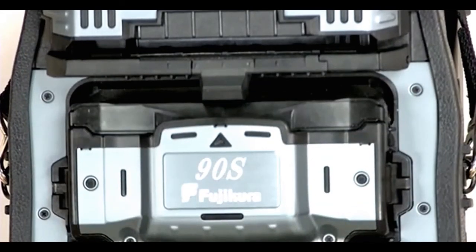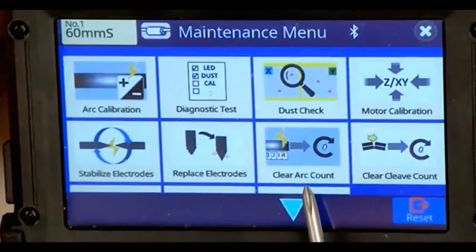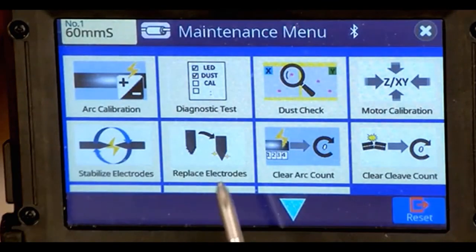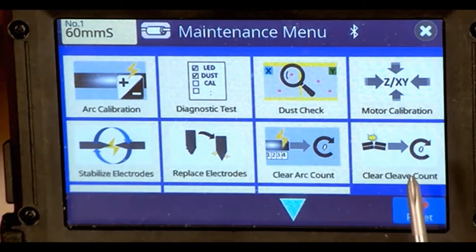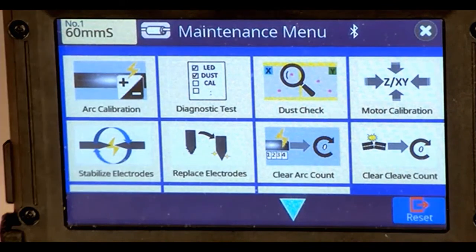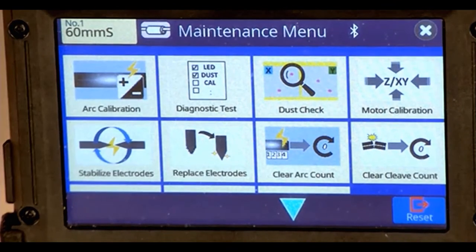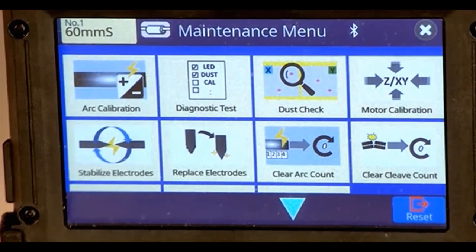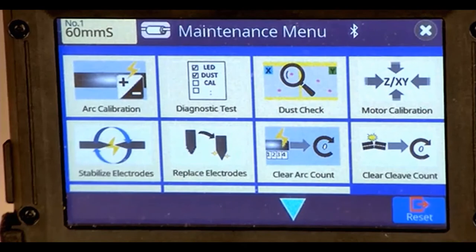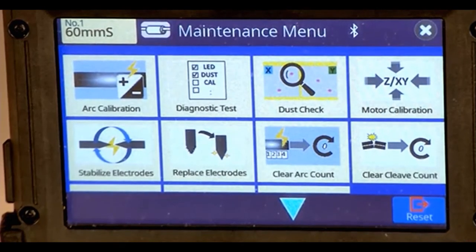Let me go back into the maintenance menu discussion. So you can clear the arc count manually, but when you replace the electrodes, it will automatically do it. To clear the cleave count, if you're using Bluetooth to manage your cleave life, you're going to go through all 16 rotational positions at blade height number 1. Then you're going to go to the next blade height and use up all 16 positions again. Then you go to the highest blade height, and you use all 16 positions. At that time, the splicer is going to tell you it's time to replace the blade.